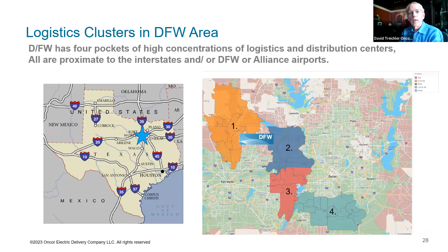Each of those 435 trucks has a 600 kilowatt hour battery. The overnight charging alone there was going to be 40 megawatts. The current load at the facility, which was a little over 100,000 square feet, was 100 kilowatts. So obviously we've got a bunch of these logistics centers on the same transformer at the same substation. But if one of them were to locate an electric fleet at that site, we would be building a separate substation for each of the buildings in these clusters.